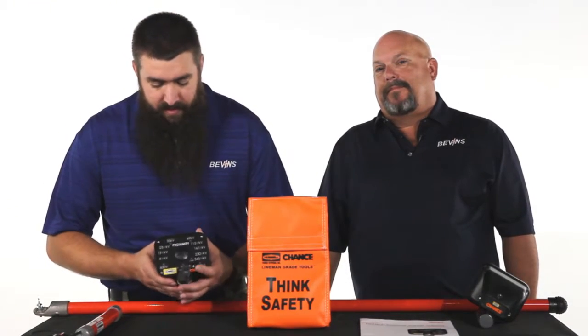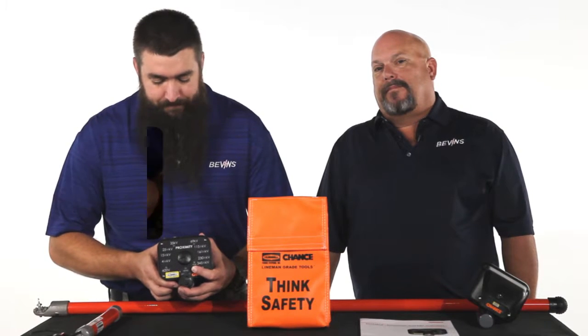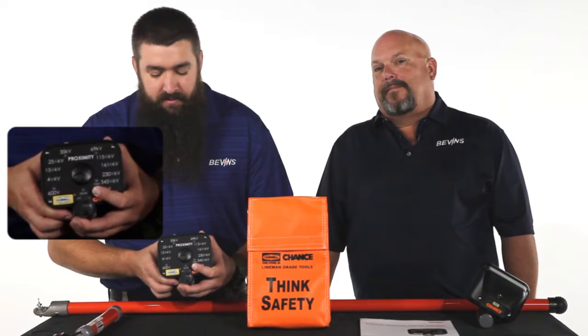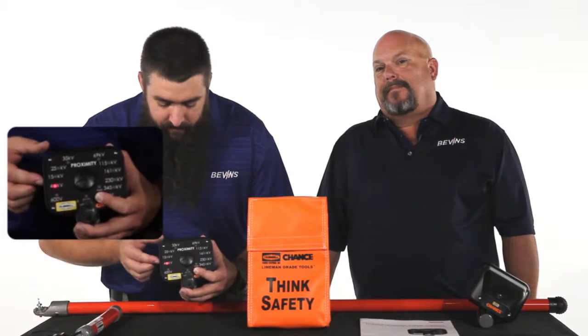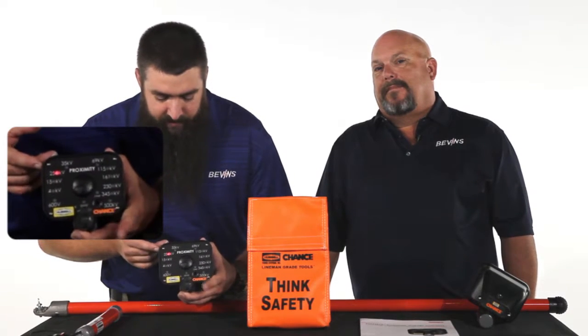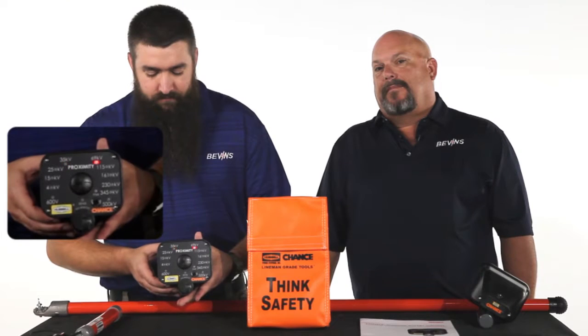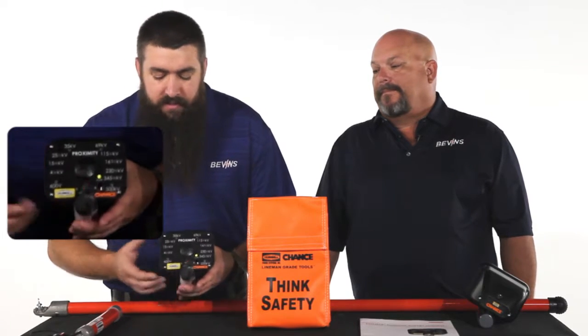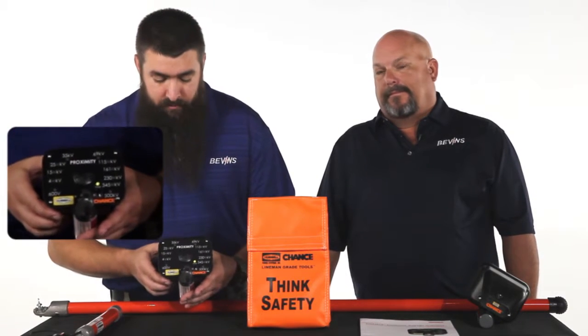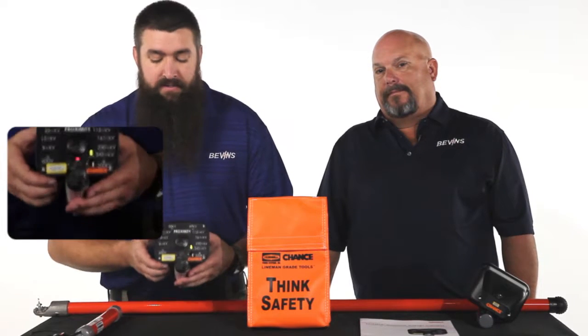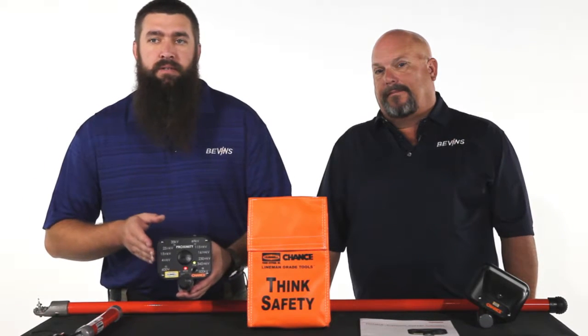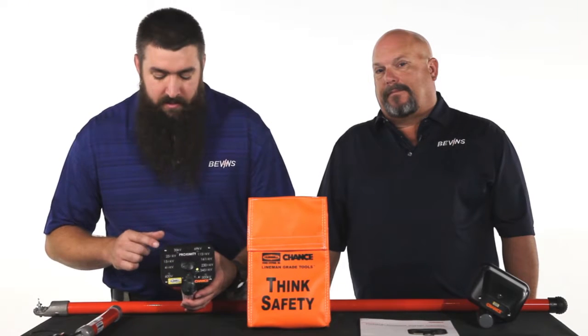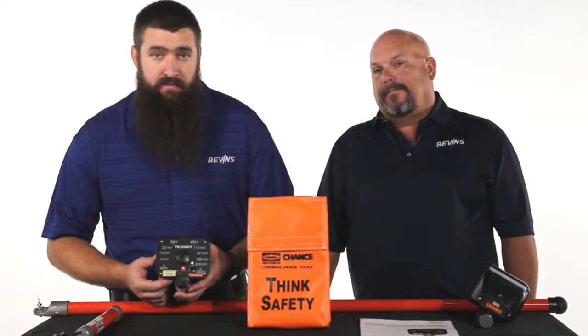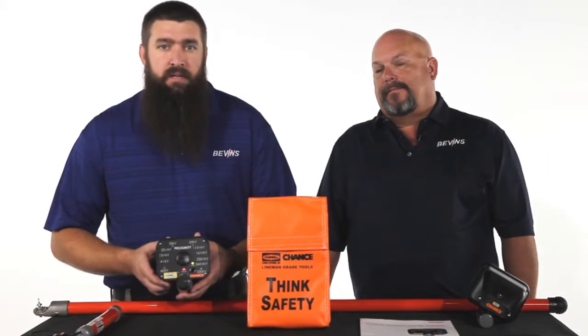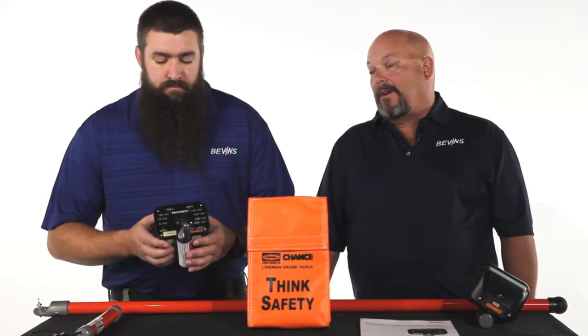So to demonstrate that now, I'm just going to press and hold the power button. There's the initial beep, and I'm continuing to hold the button. We're going to let the LED slowly climb to 25 and let go. So then it completed its normal boot up sequence and self-test, and now it's in the advanced range mode, and it will not display the LED or the audible alarm on any voltage below 25 kV, with the exception of the sense light, as I mentioned. So, which is always working. Yeah, the sense light, we cannot disable it.